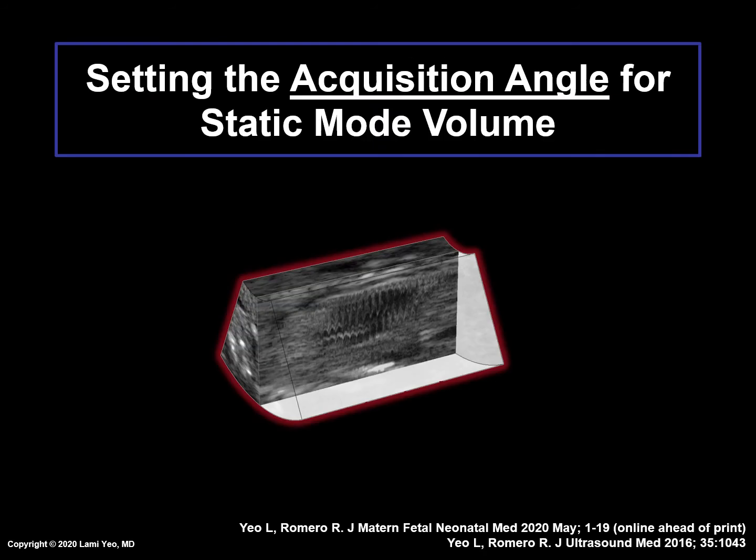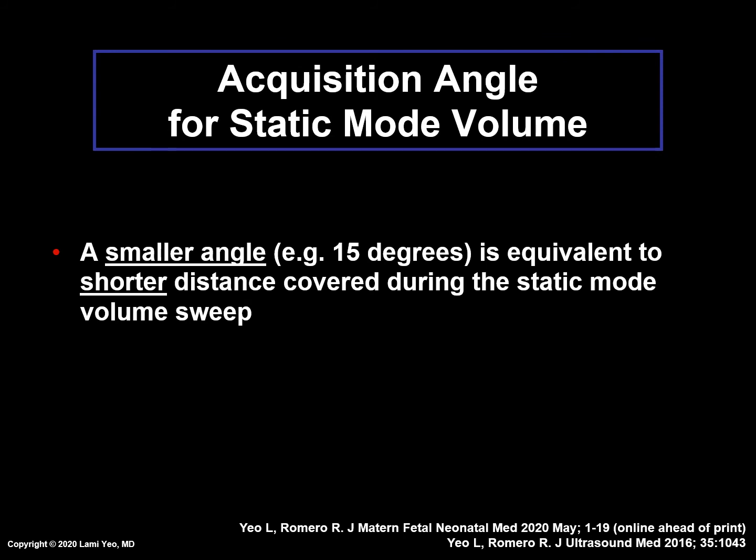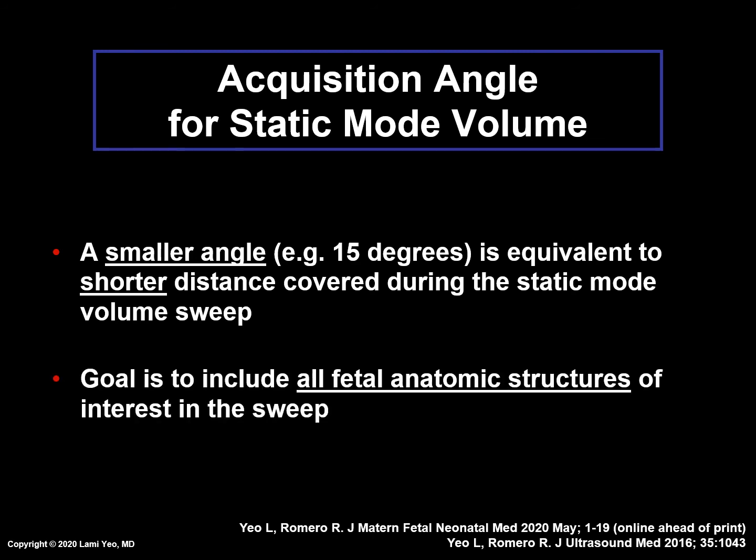Although there is no acquisition time to set, the acquisition angle should still be determined prior to obtaining the static mode volume. The angle determines the acquisition depth. A smaller angle, such as 15 degrees, is equivalent to a shorter distance being covered during the static mode volume sweep. However, it is important to program the angle to a minimum value so that all fetal anatomic structures of interest are included in the sweep.